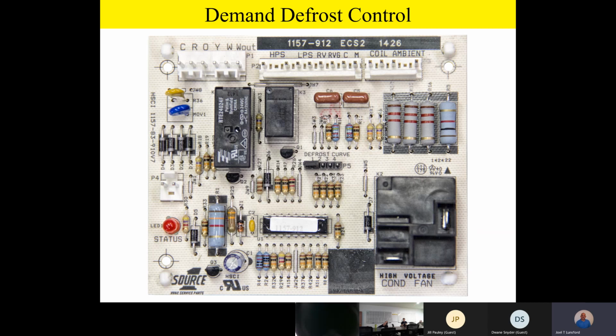So one more time, whenever we go into defrost, we're going to shut the outdoor fan off. The reversing valve is going to switch into the cooling mode of operation, and we're going to output a signal from the board outside to bring on auxiliary heat to temper the air so you don't freeze the homeowner out during defrost. So again, the demand defrost control has two sensors, a coil sensor and an ambient sensor, and those sensors are constantly being compared. Those temperatures are constantly being compared as far as when to go into defrost.